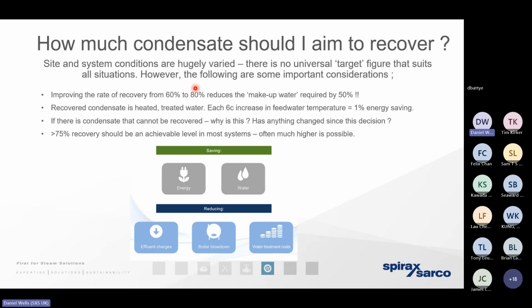So I just want you to look at that rule of thumb. If we're able to increase the condensate return from 60% to 80%, then it means that we don't need to consume as much water. A lot of sites have got water scarcity KPIs, so that can have a huge benefit. And we then don't need to chemically condition that water. And if we're getting more water back to the hot well, if we can increase the temperature of the water that's held in storage in the hot well by 6 degrees up to a maximum of 85 degrees, then the benefit is going to be approximately 1% on fuel cost savings. So one of the most beneficial and efficient things we can do is ensuring that we get as much of that valuable high temperature hot water back to the boil house as we can.